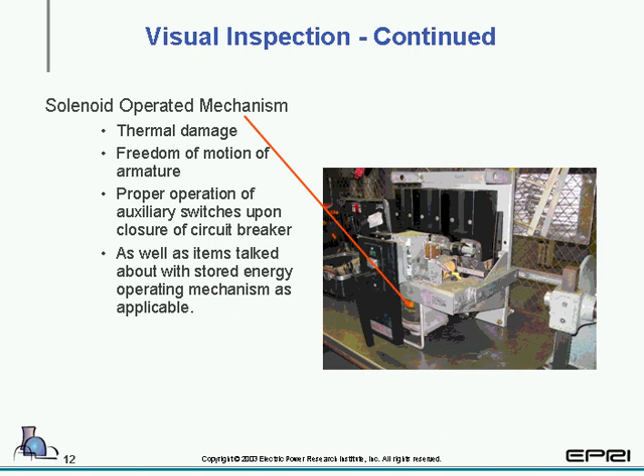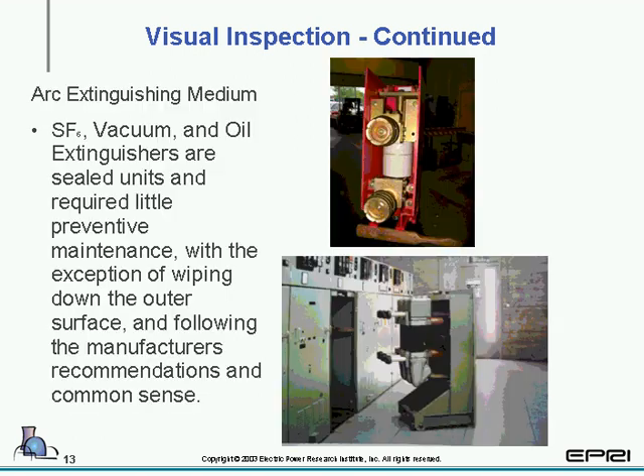Along with the last slide, you may have a stored energy. Or excuse me, the last slide was the stored energy. This particular slide is a solenoid-operated mechanism. On top of all the items that we talked about with the stored energy, you're also going to want to take a look at thermal damage, freedom of movement of the armature, to verify that the coil is in good shape, as well as the mechanical parts of the operating mechanism.